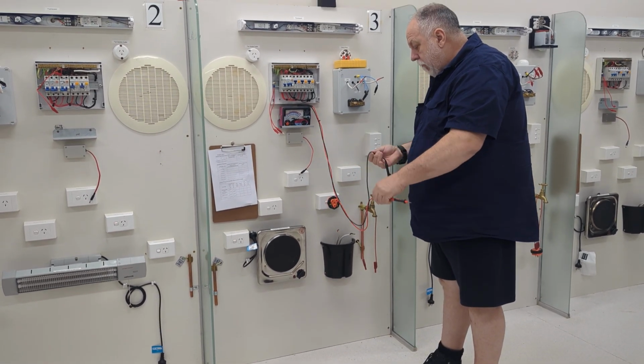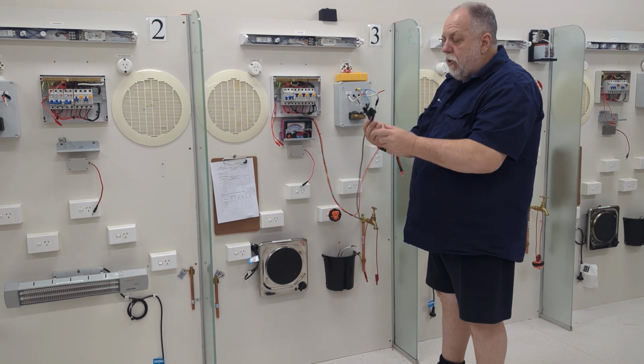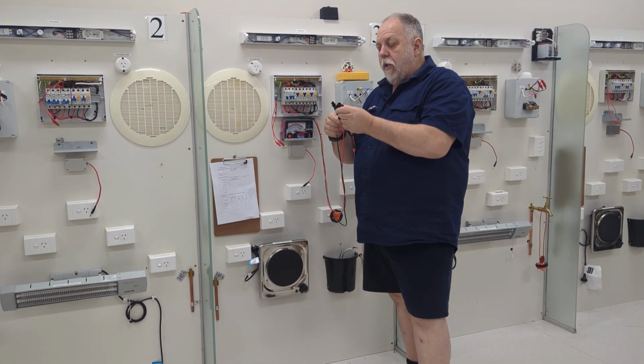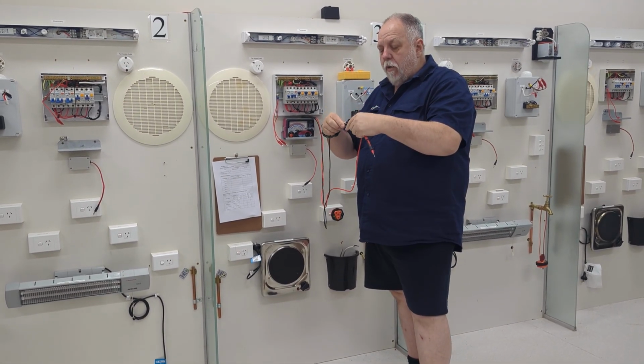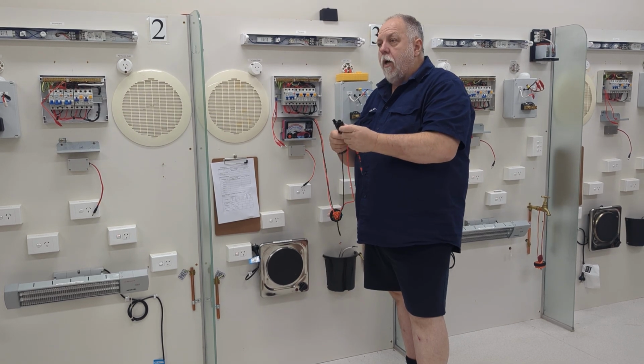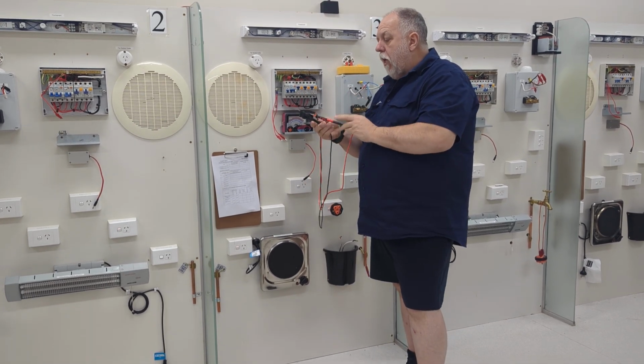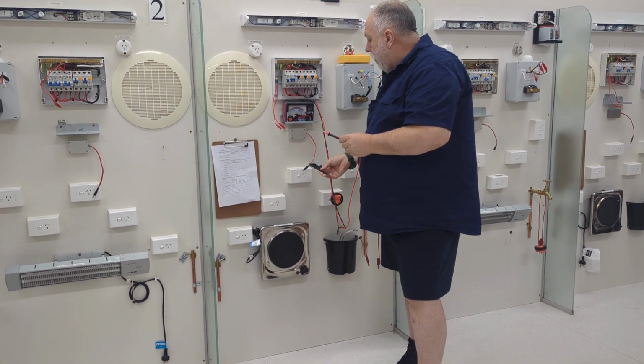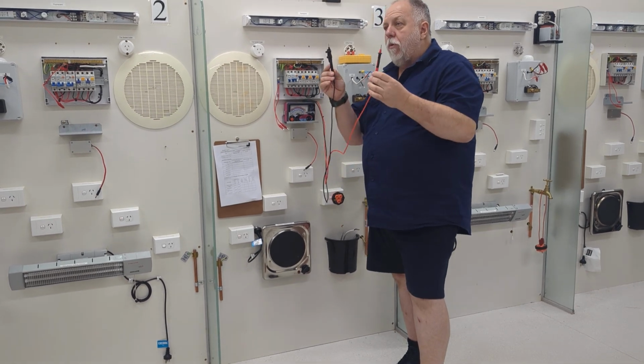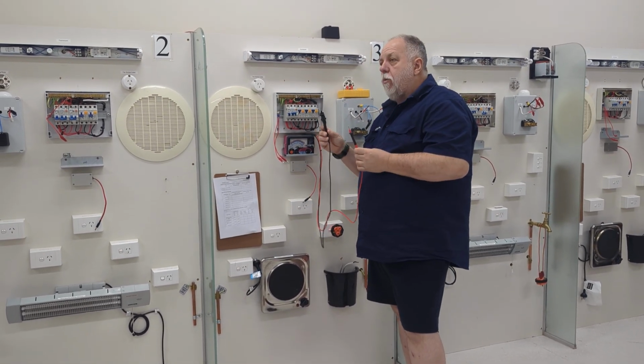Some leads you get, you might have the option, I'm just showing you on this, we've got a clamp so you can actually take this out and put the clamp in, right? Or you might have the probe, okay? The only problem is when you've got the clamp, if you have to test into a power point, you won't be able to use that, all right? So you can either do it at the switchboard end.